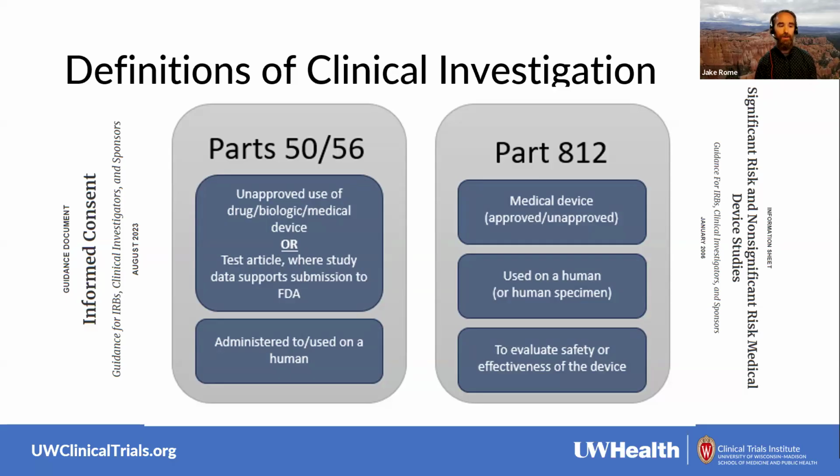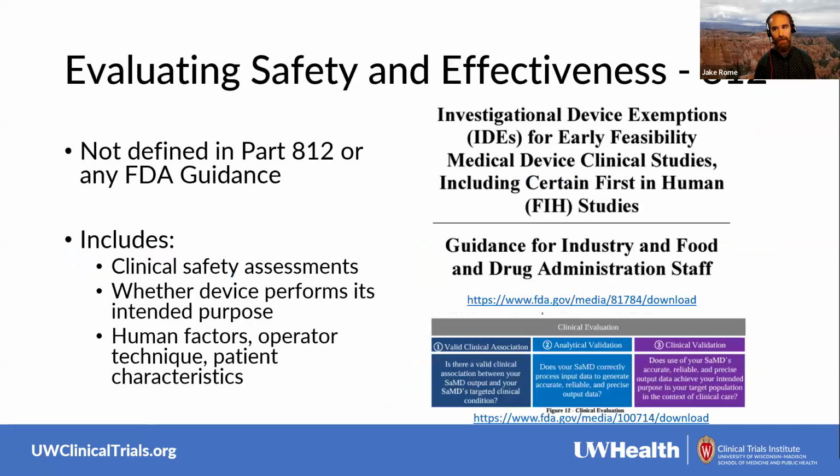And so there are two things about this definition that are distinctly different from the drug and biologic clinical investigation definition. One, it applies to specimens. And again, the FDA doesn't care if the specimens are identifiable or not. And there also has to be an evaluation of safety or effectiveness of the device, right? With a drug, if you're administering it, you get brought into the FDA's purview. With a device, you have to be evaluating the safety or effectiveness of the device for the Part 812 requirements to apply.